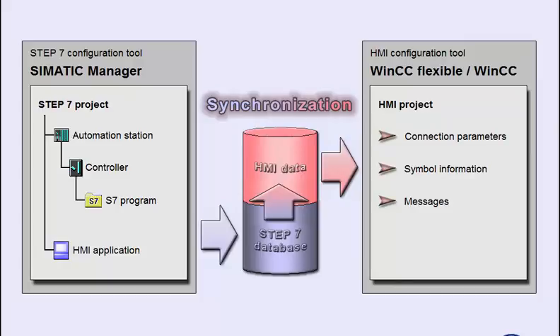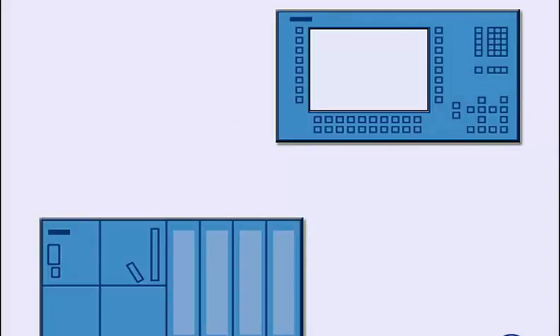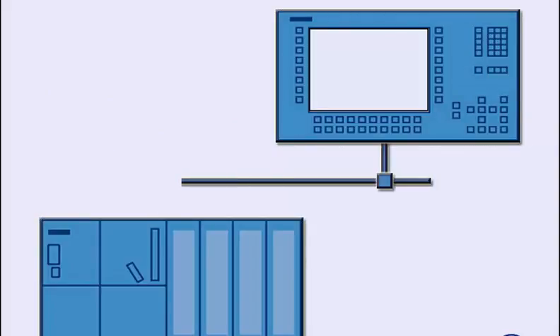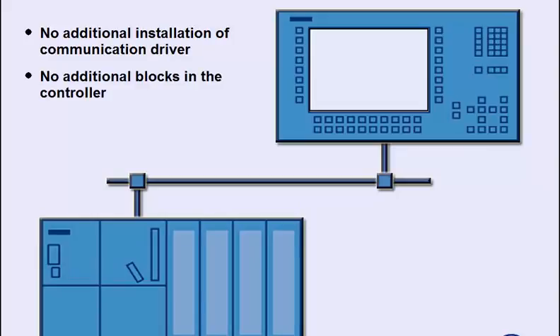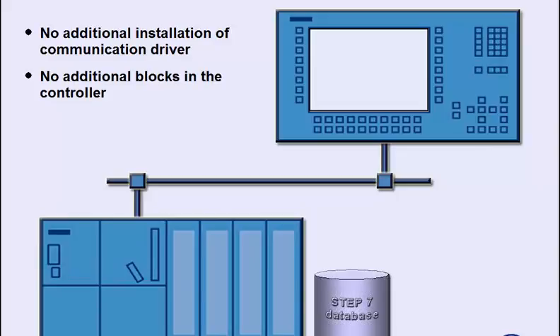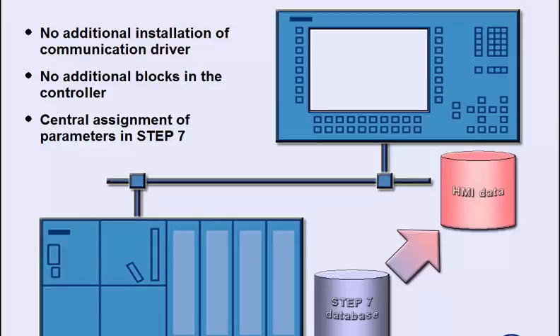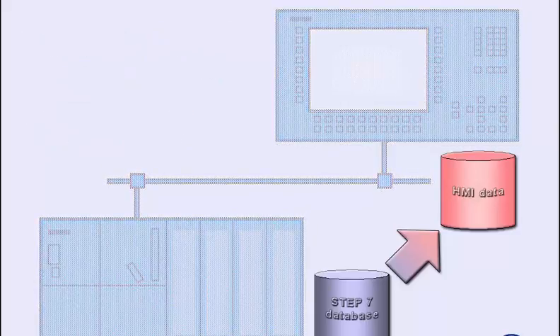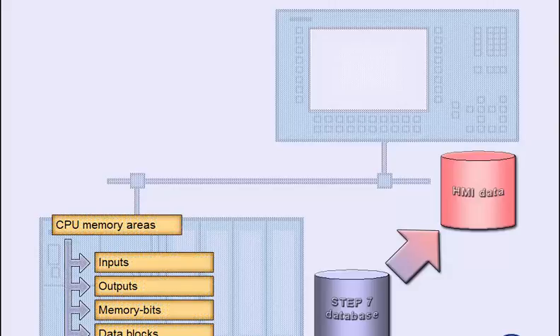Now take a closer look at how HMI configuration is made easier by integration into Step 7. The link between the operating device and the automation system is limited mainly to the physical connection. All necessary drivers have already been installed with the SIMATIC HMI software. The system communication does not need any special blocks in the controller's user program. The connection parameters have been taken from the Step 7 database. Therefore, no extra configuration is required to connect the HMI system to the network.